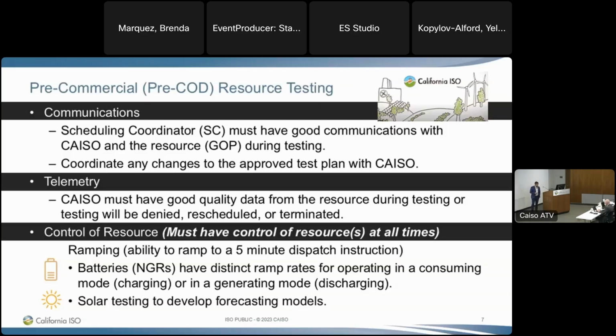Okay, ramp rates. This one has come up quite a bit. So for batteries, we actually have, again, 14,000 megawatts of batteries. The ramp rates on batteries, you can do instantaneous ramps essentially. So if you're a 500 megawatt BESS, you basically have 1,000 megawatts of capacity. Essentially, if you're at 0, you could go 0 to 500 instantaneously. Is that good for the grid? No. So we've had to do a lot of outreach for those resources to ensure that they linearly ramp, because in reality, you're going to get a 5-minute dispatch. So the rule of thumb is to ensure that your ramp rate matches that 5-minute dispatch.